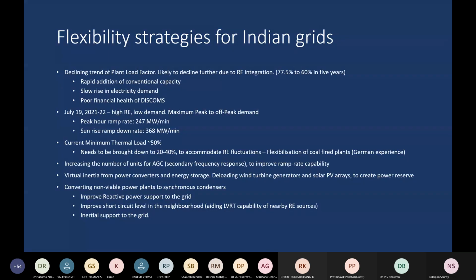But today, when you talk about renewable energy integration, you talk about system strength and you talk about system inertia. System strength is referring to the amount of short circuit capacity at a particular bus when there is a fault at that bus. So you want that the system strength should be very high, which means that the short circuit level at that bus should be very high, which means that the Thevenin's equivalent impedance at that bus will be very low. So system strength and system inertia can be increased by the synchronous condensers. The capacitors cannot do that. Similarly, the STATCOMs and SVCs cannot do that. So therefore, non-viable power plants may be converted to synchronous condensers.